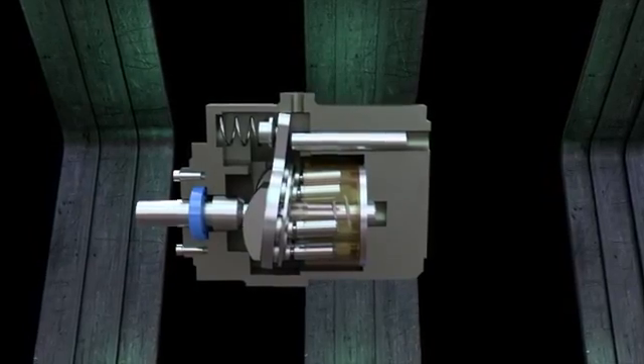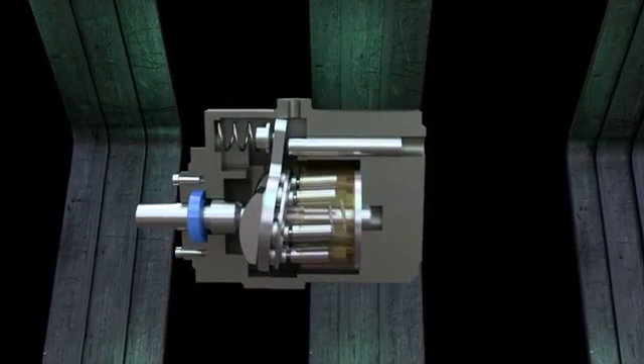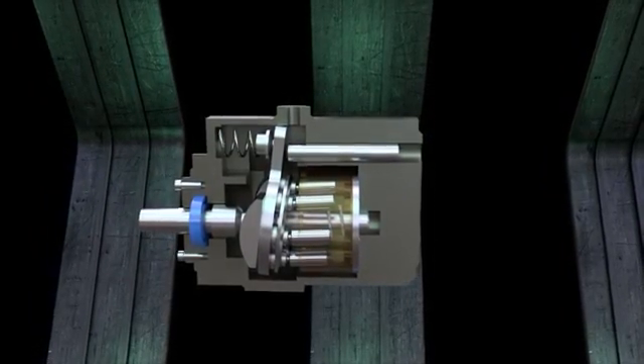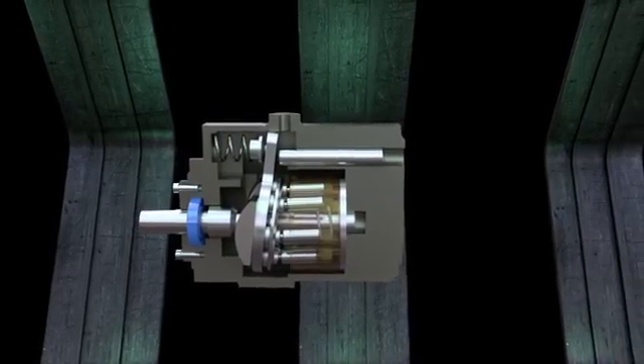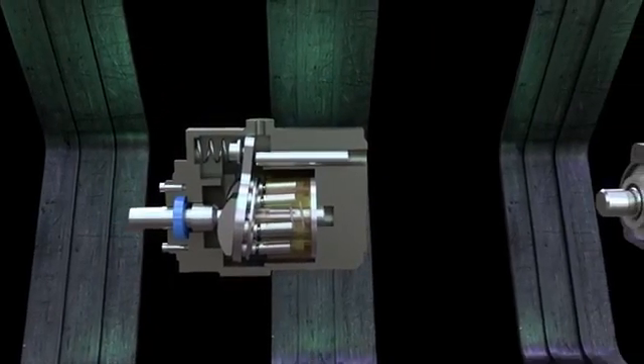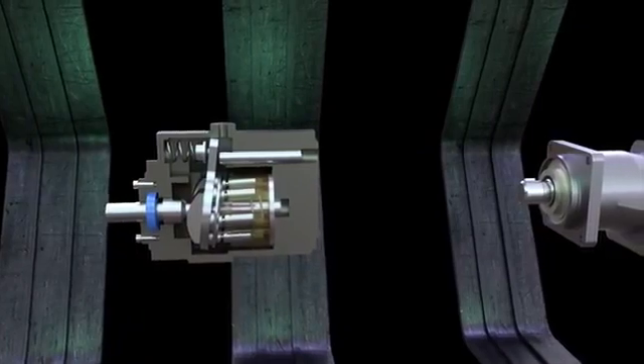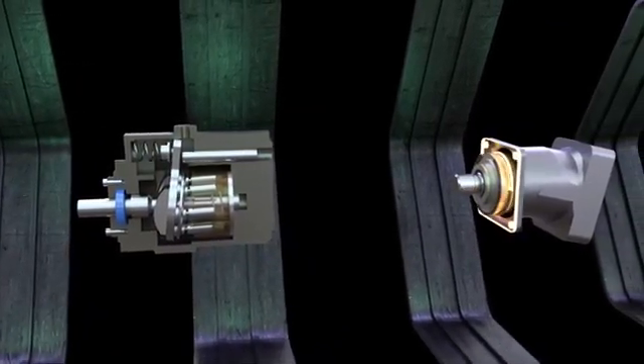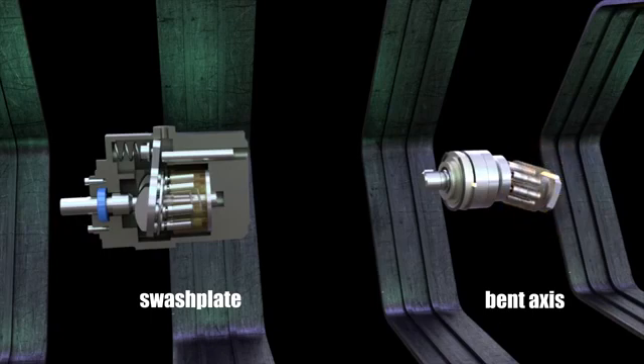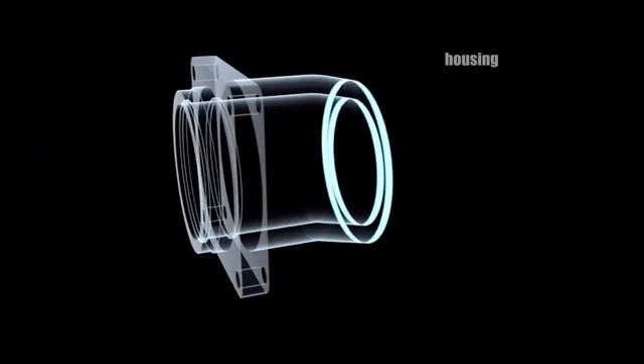Converting the rotational motion of the input shaft into the translational motion of the pistons is possible due to the inclined position of the bent axis, or the swash plate on which they rest. In the first case, the device is called a bent axis pump. In the second case, it is a swash plate pump. Let's try to figure out how these pumps can pump fluid. First, let's check the pump design. Let's take an adjustable bent axis pump as an example.